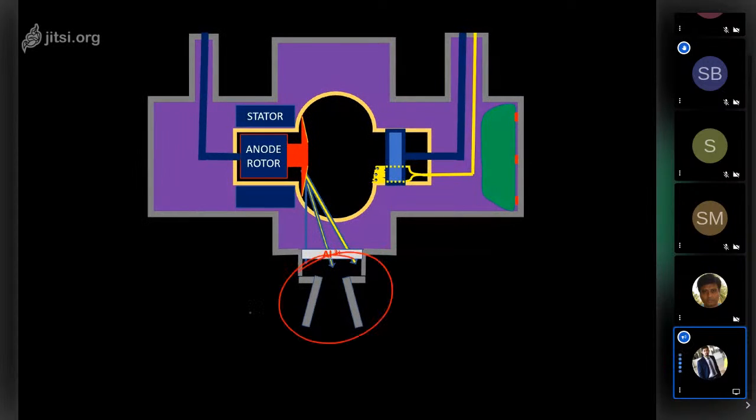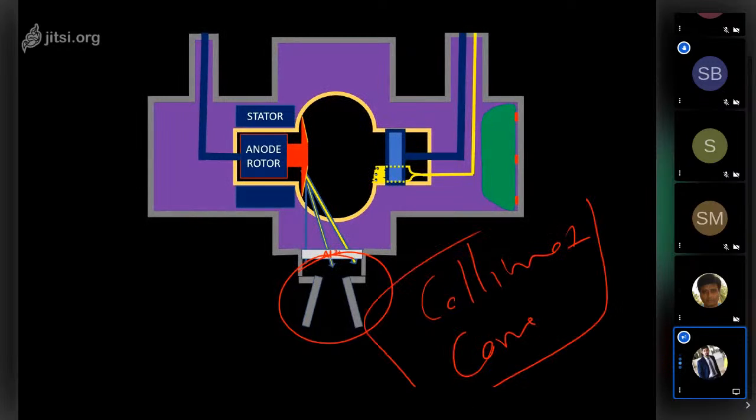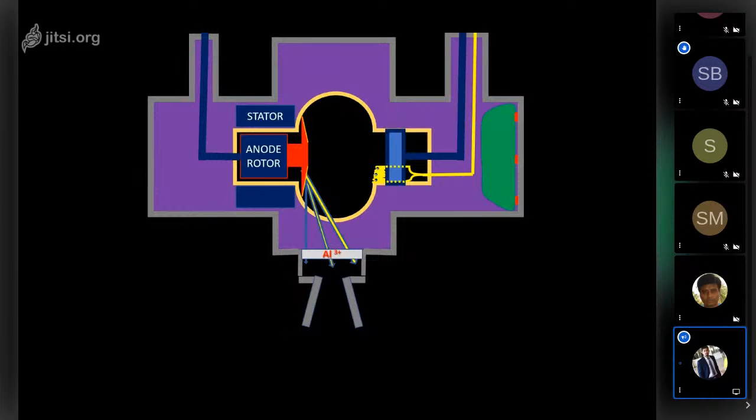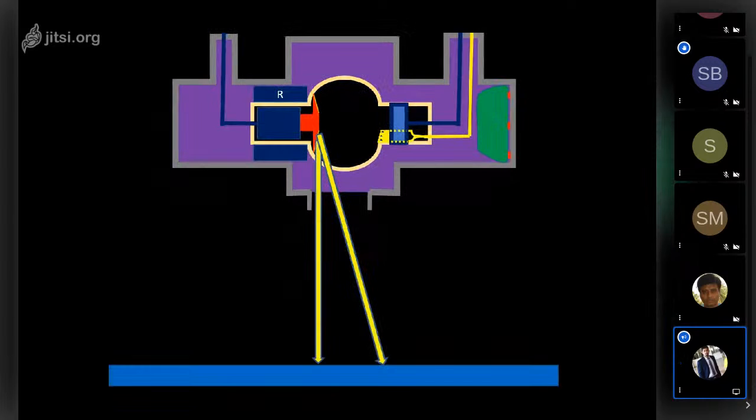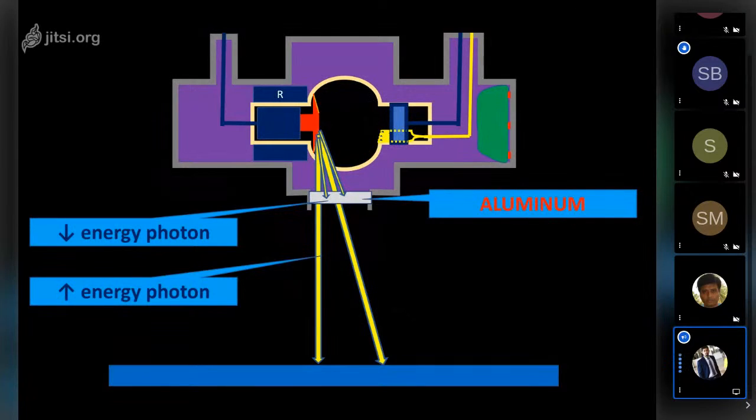And we have beam restrictors, that is the collimators and the cones. So this will reduce the scattered radiation. Again, we have discussed all this. So the use of a filter is nothing but to reduce the low energy X-rays from passing through. This is the grid which is present between the patient and the image receptor. What will the grid do? The grid will prevent the scattered radiation.